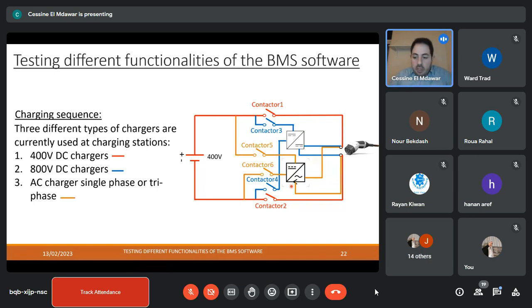Again, these detections are all done in the BMS, and it should make sure that in the HIL rig, if I provide it with a 400 volt source, contactor 2 and contactor 1 are closing. If I provide it with 800 volt, I need to check that contactor 3 and contactor 4 are closing. I need to make sure only these are closing and no other contactor. We don't want several contactors closing - if contactor 3 and 4 close and then contactor 2 as well, we don't want that. So these are all tested in the HIL rig and designed by the BMS. I'll go back to the BMS team and tell them your contactor sequence control is wrong, please fix it if this is not happening.